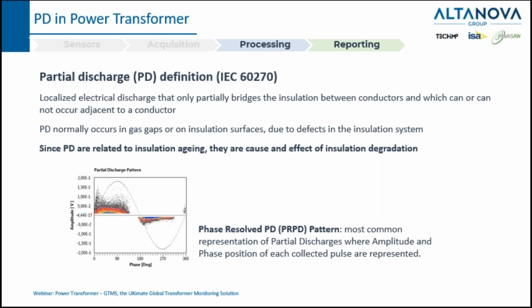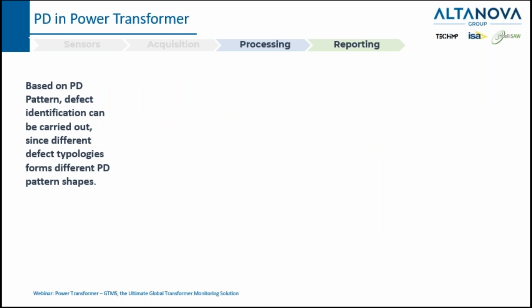On the bottom here, you can see a picture of a typical representation of the acquisition of partial discharge. The name is phase resolved partial discharge, PRPD pattern. It is the most common way to represent the amplitude, here on the vertical axis, and the phase angle, the phase shift, on the horizontal axis. You can see here also different colors. Colors are related to the intensity, to the number of pulses acquired for each cycle. Based on this pattern, defect identification can be carried out because different defect typologies have different PD pattern shapes.